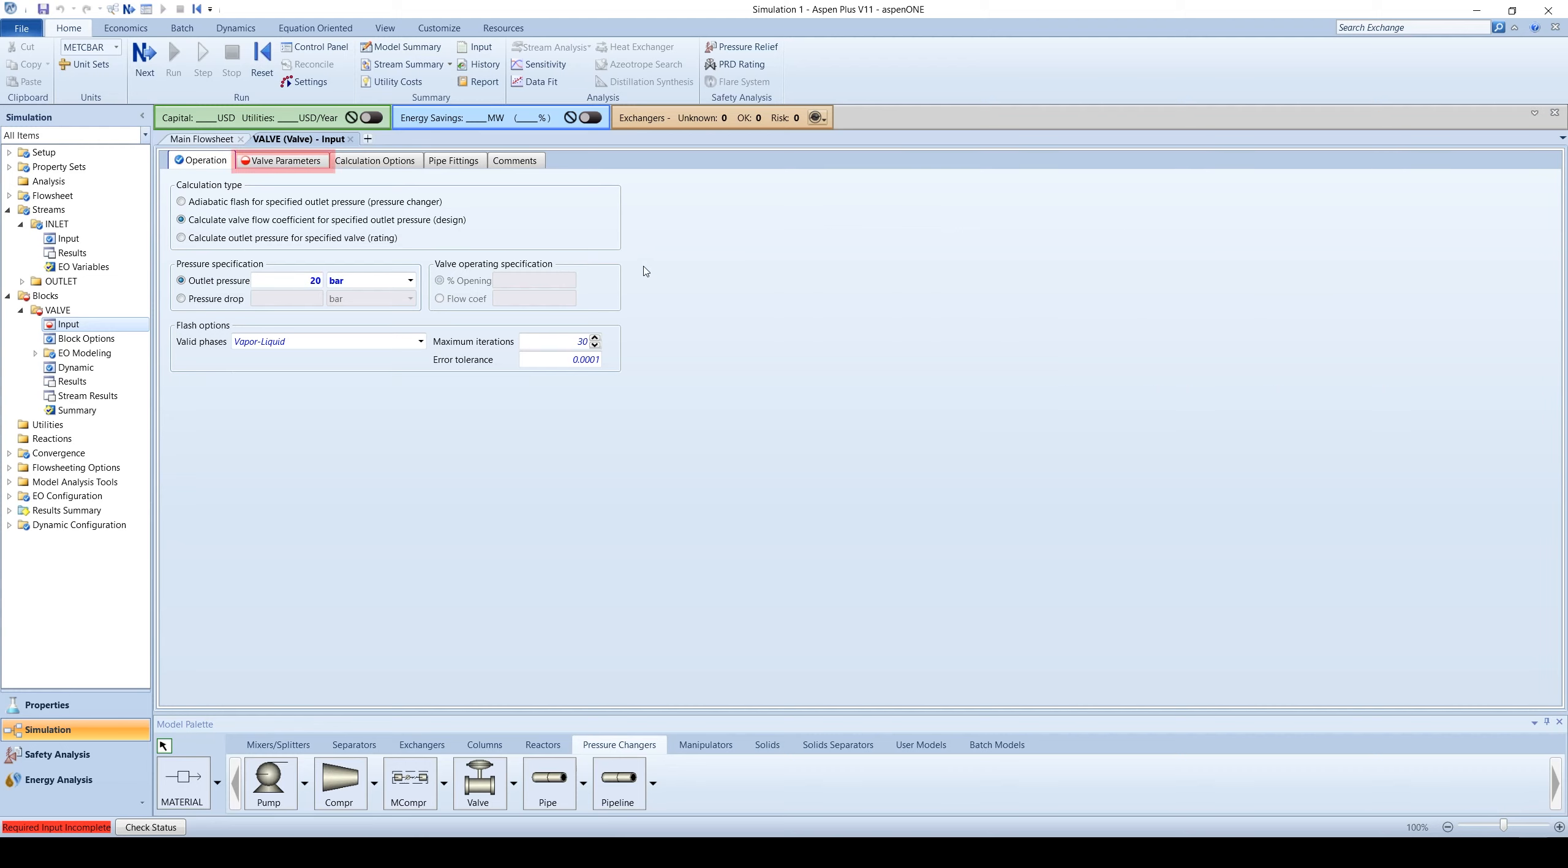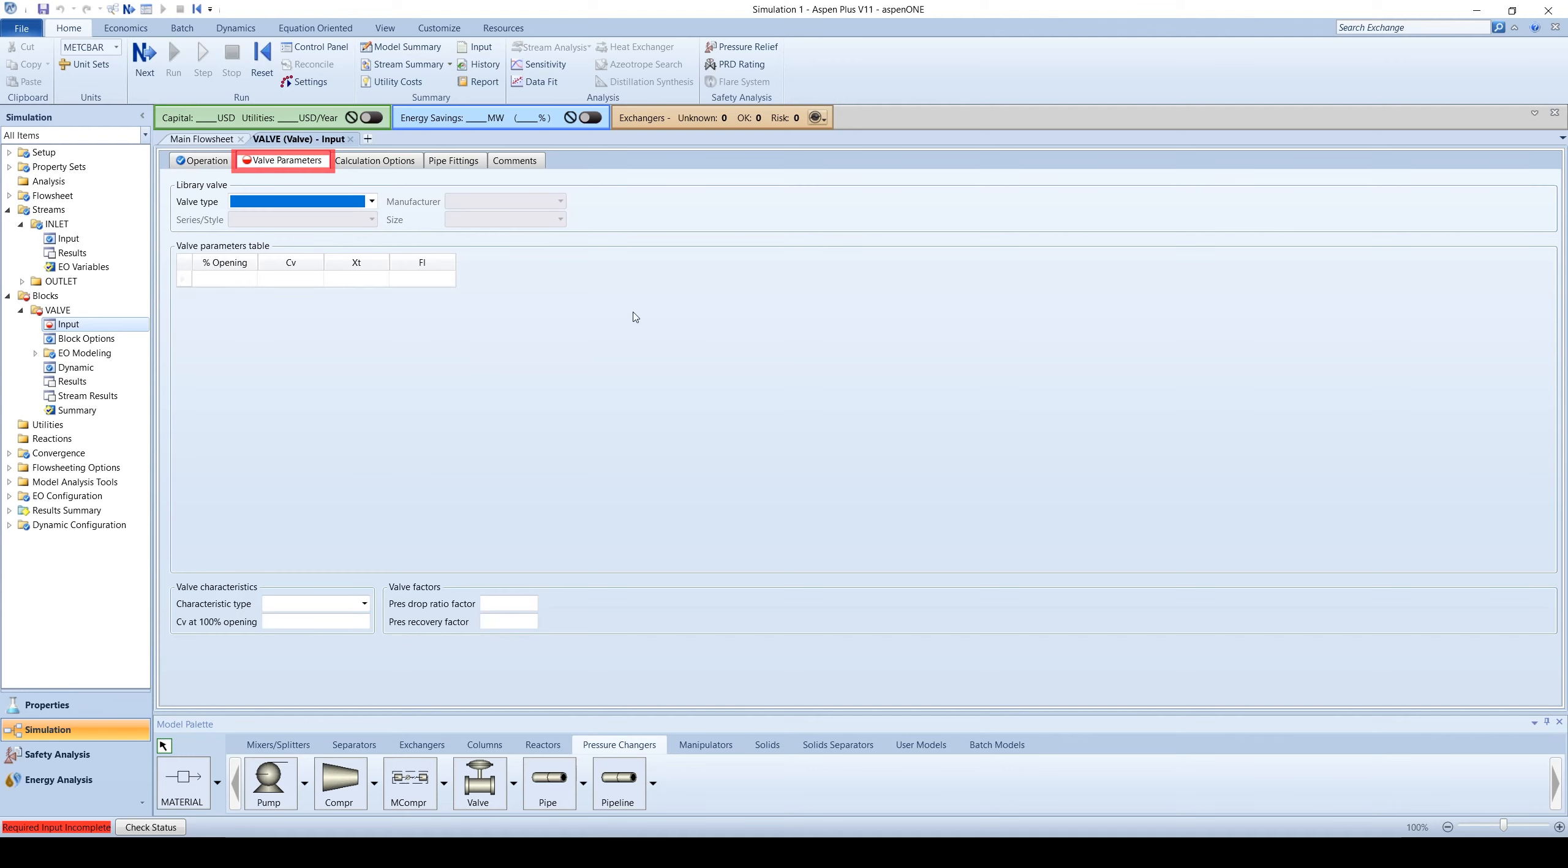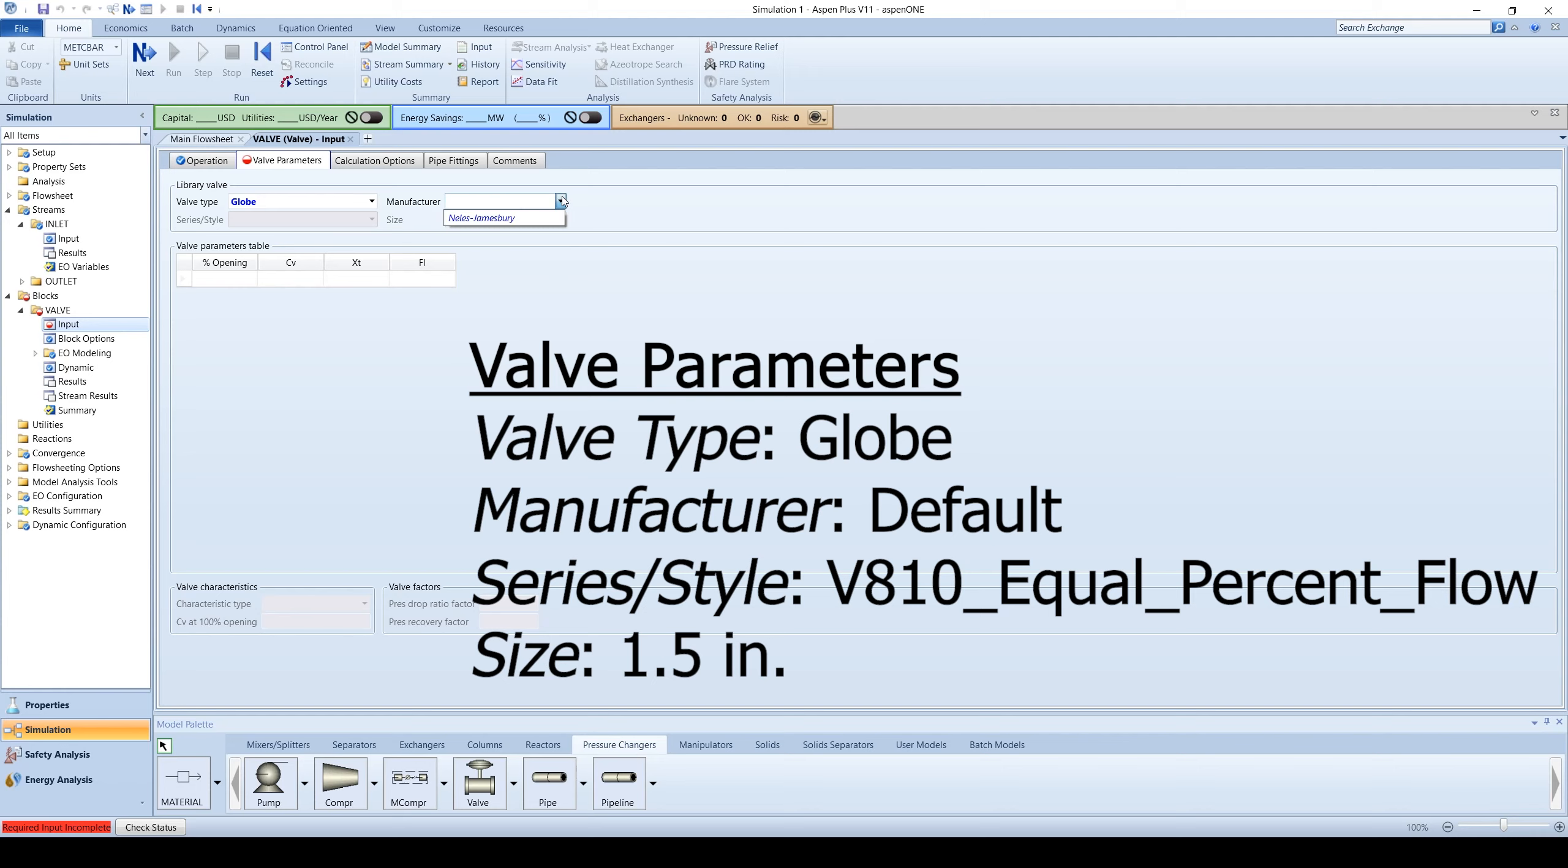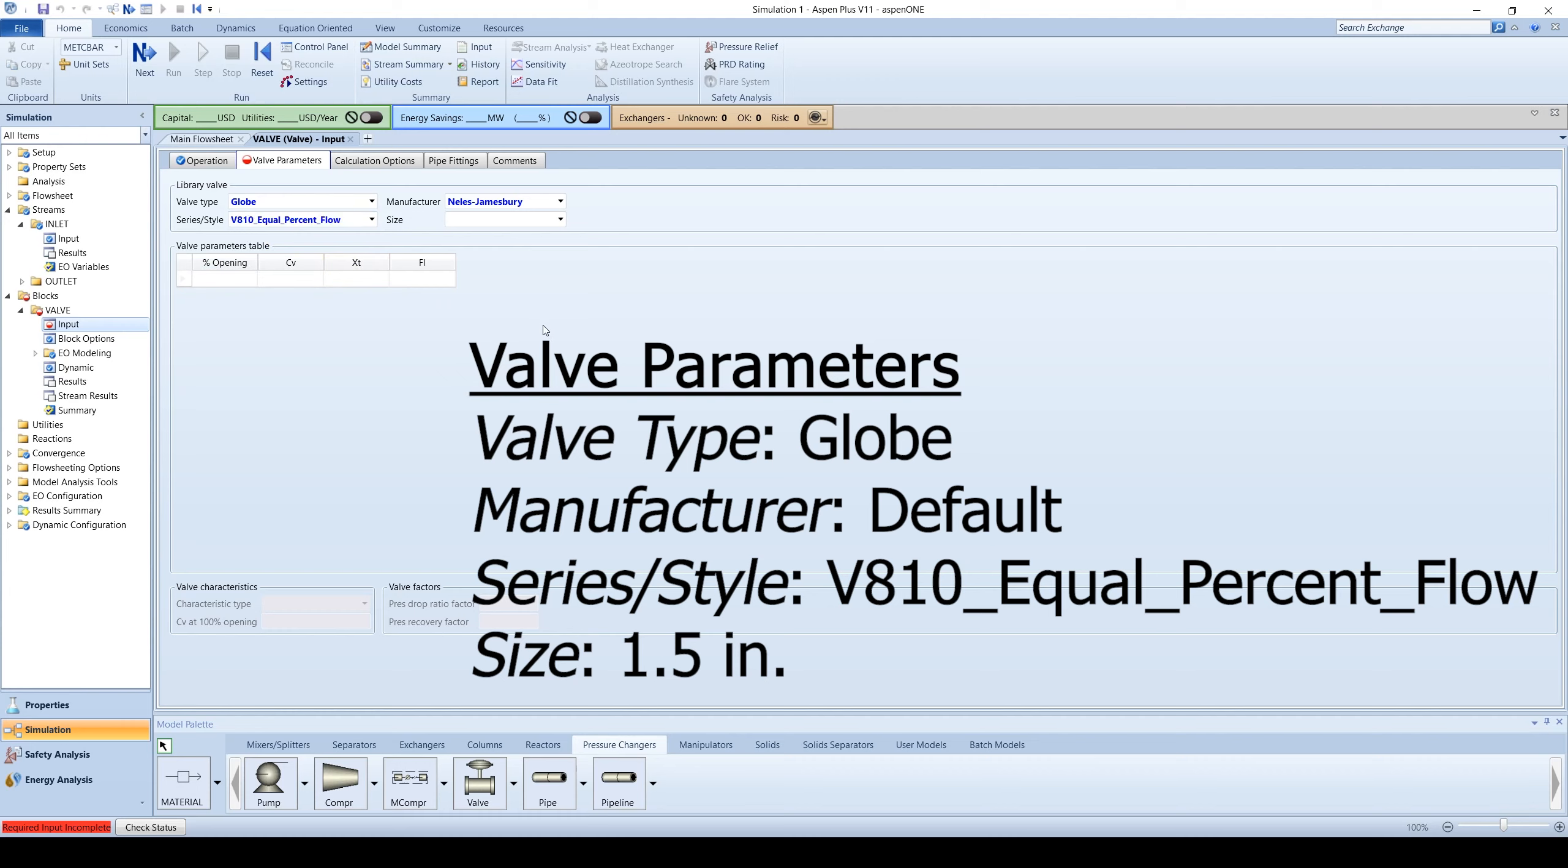Next, go to the valve parameters tab. Choose the globe valve as the valve type and choose the default manufacturer. Select V810 equal percentage flow as a series in style and the size is 1.5 inches.